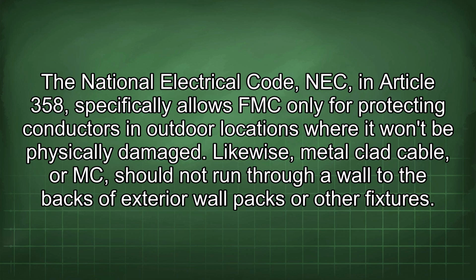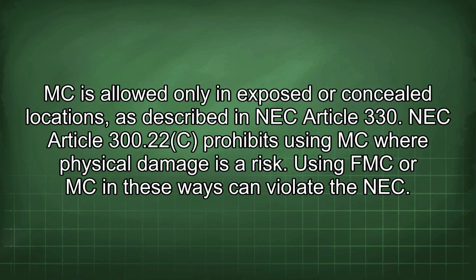won't be physically damaged. Likewise, metal-clad cable, or MC, should not run through a wall to the backs of exterior wall packs or other fixtures. MC is allowed only in exposed or concealed locations as described in NEC Article 330. NEC Article 300.22c prohibits using MC where physical damage is a risk. Using FMC or MC in these ways can violate the NEC.